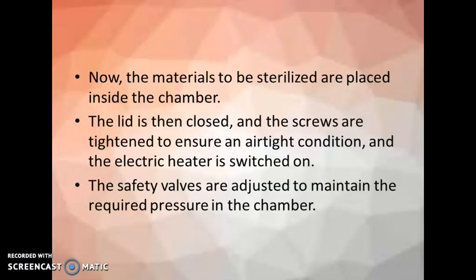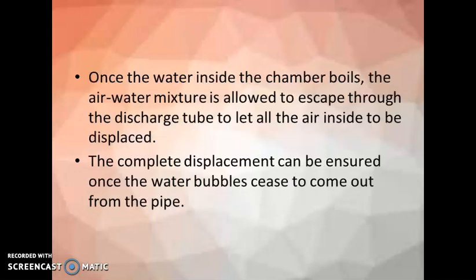Now coming is the continuation of the first part. After the materials were placed inside the chamber, we close the lid and the screws are tightened to ensure an airtight condition, and then we can switch on the electrical heater. The safety valves are adjusted to maintain the required pressure inside the chamber. So that's why the safety valves are crucial in an autoclave.